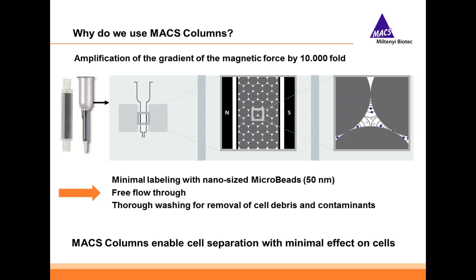The column is what really sets MACS apart from other technologies. The column amplifies the magnetic gradient by 10,000-fold. Here on the left you can see a few columns, and on the right you can see how the spheres inside the column amplify the gradient of the magnetic force. This ensures a thorough magnetic gradient throughout the column, enabling minimal labeling with the nano-sized microbeads. It provides free flow-through of the cells through the column and thorough washing for removal of cell debris and contaminants. In conclusion, the MACS columns enable cell separation with minimal effects on the cells.